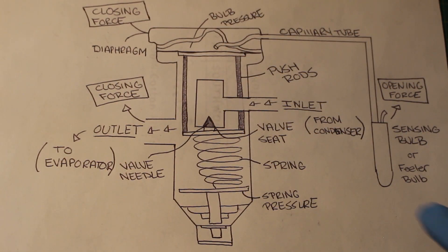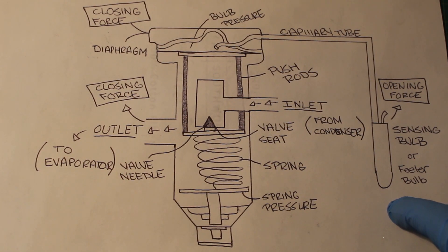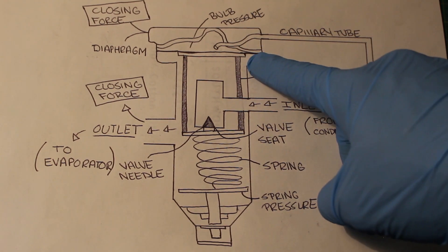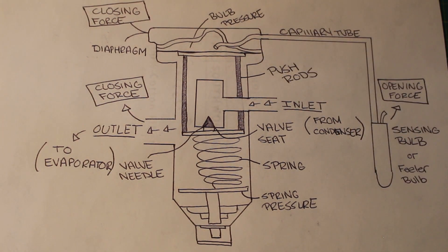Starting with bulb pressure: the sensing bulb or feeler bulb — the bulb pressure comes from the sensing bulb that is mounted at the outlet of the evaporator, which senses suction temperature and drives the diaphragm down if there is an increase. This is your diaphragm right here, at the top of your valve.